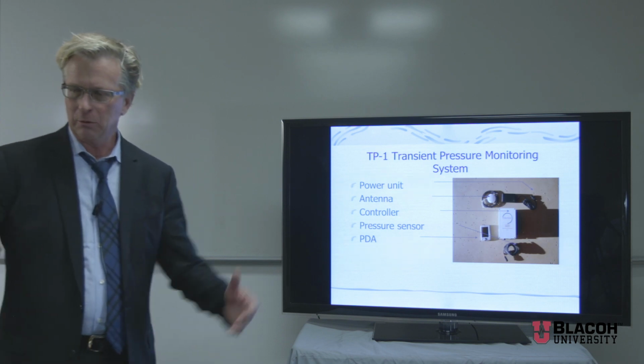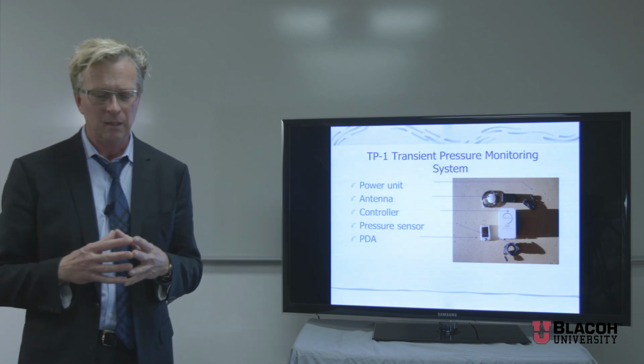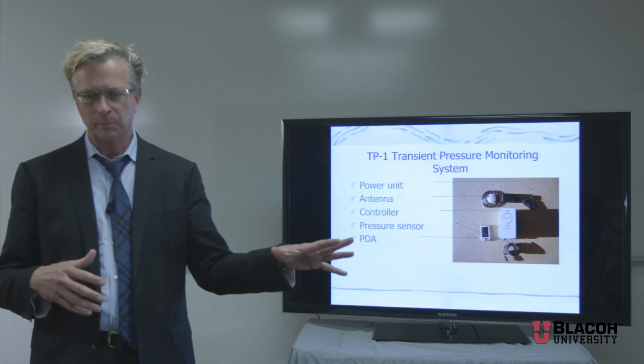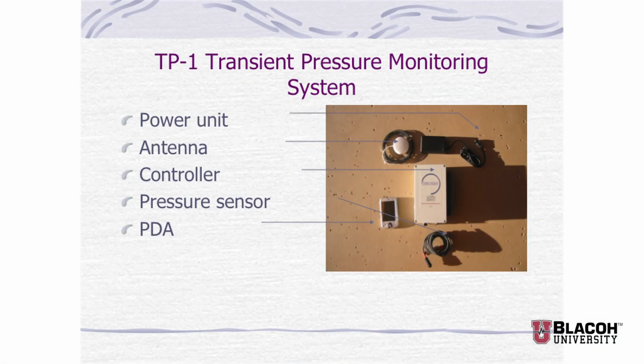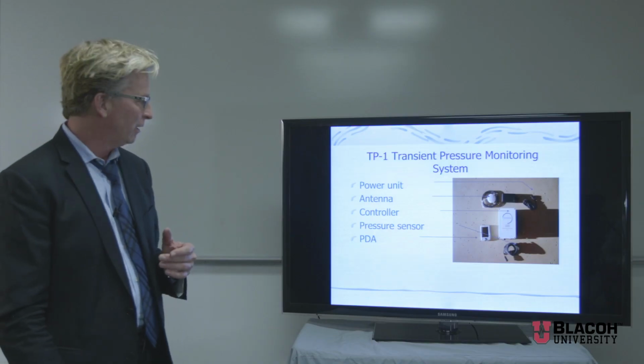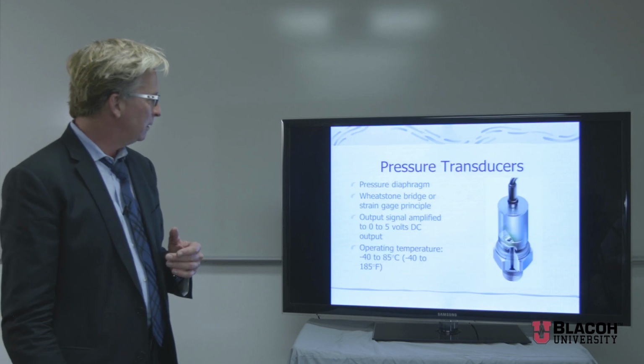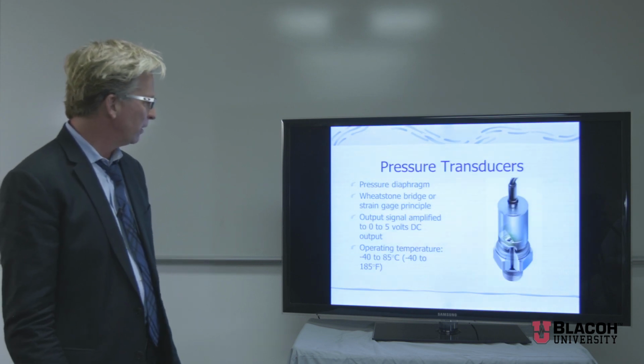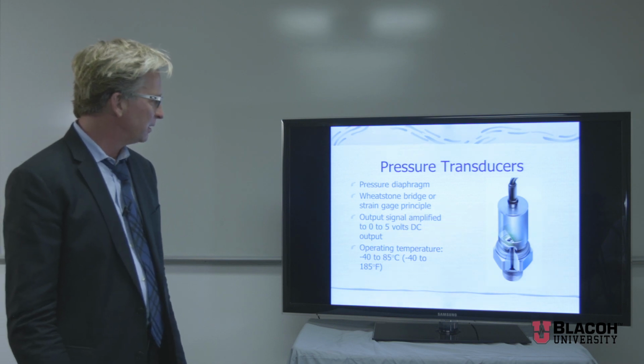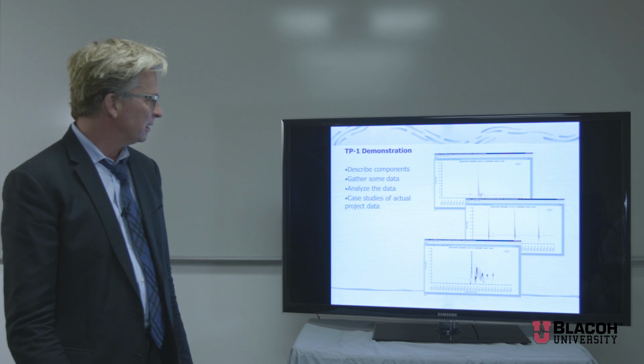And what's interesting, like you had 2 pressure transducers on your system. What we can do is put one transducer at the pump station or a refinery, and one all the way back at the dock. It has a GPS which records the location of the test, but also synchronizes the devices from a time step, so you know exactly, to the 100th of a second, when the event occurred, so that we can review the data. The transducer is sending a 0 to 5 volt signal into the computer system, and these are just some examples of the data that it's recording.